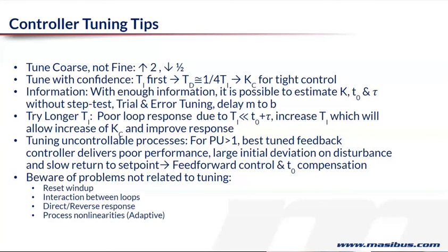If you have some idea about the response of the process, like its oscillation period, you just set your Ti to that oscillation period, set your Td to 1/4 of the integral, and now keep changing your P band to get the accepted response. A very simple and fast method.